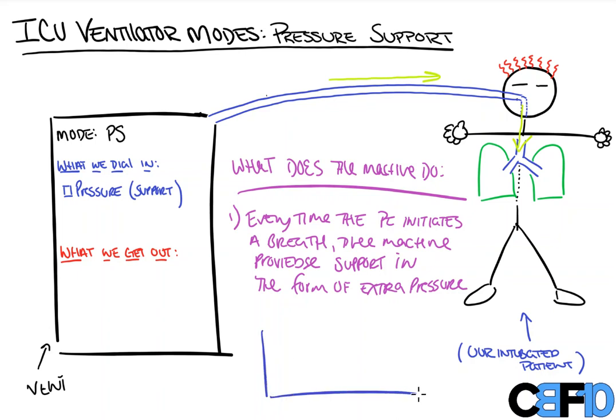We'll draw our graph here, with the y-axis as pressure and the x-axis as time. What the machine is going to see is there will be — shown here in green — a negative pressure sensed by the machine because the patient is starting to inhale by themselves, and then the machine will deliver extra pressure up to help support their breath. Then it comes back down to base. As the patient triggers a breath again, it'll sense that negative pressure and kick up the amount of pressure being delivered to the patient.